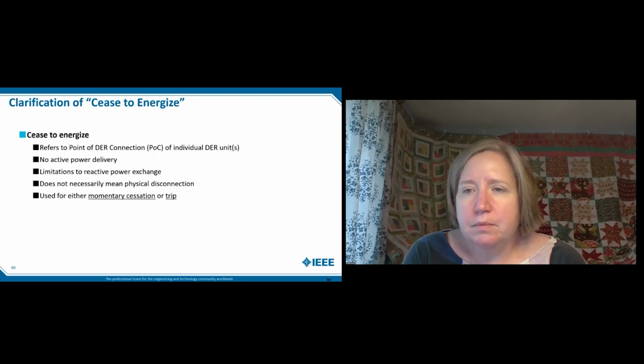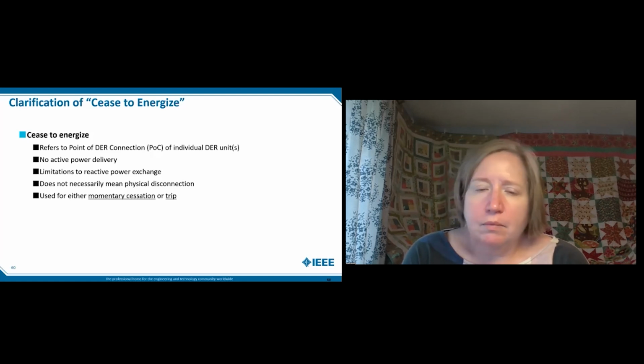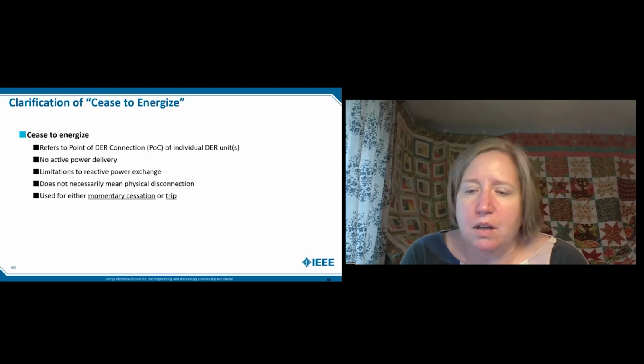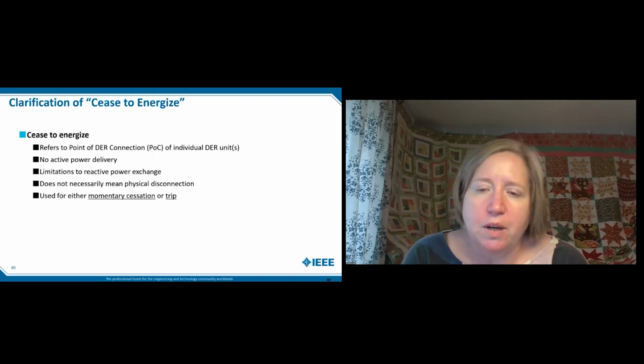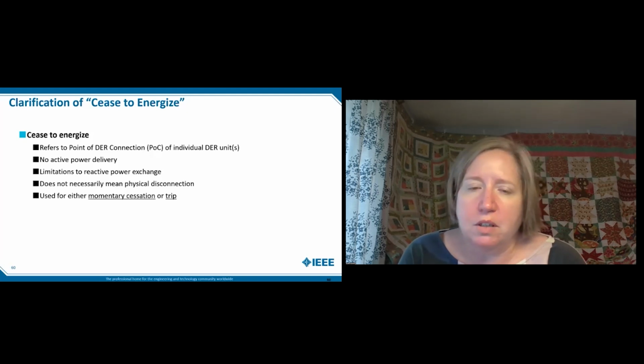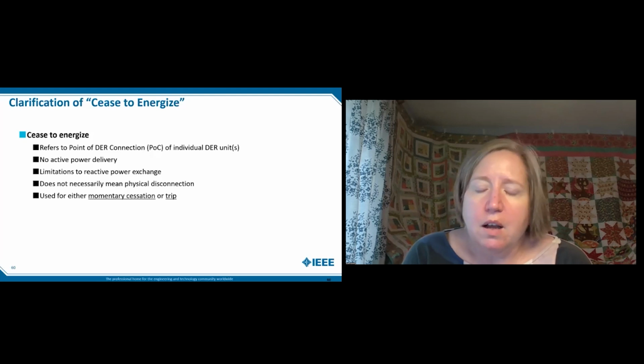For your own under frequency load shedding, how big are the blocks of load you drop? Is it a substation or even multiple substations at a time? We do it at the feeder level. Okay. So we won't even clear an entire station. We will clear specific feeders. We are in discussions about, if we run across a feeder that's becoming high penetration that has load shedding on it, do we want to talk to planning about moving that load shedding to a different feeder? We haven't run into that yet, but we know it's coming.